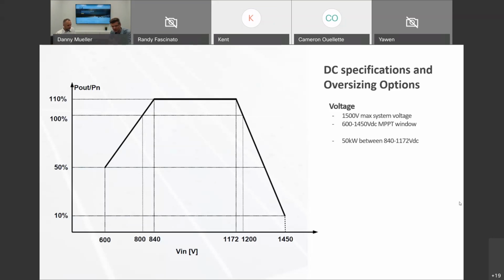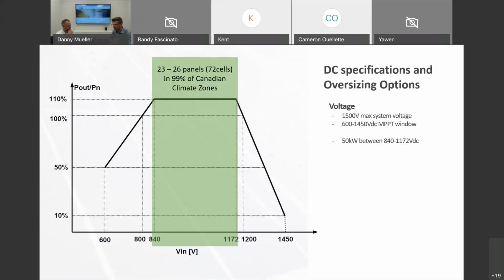The inverter starts at 600 volt. That's typically on the very, very low end of the spectrum, and if you've done your string design properly, you will never reach that point, but it can go down to those lower voltages in a partial shading condition, for example. The system voltage, as Danny mentioned, is 1,500 volts, so you cannot exceed that voltage under any circumstances, otherwise the inverter and DC capacitor will fail. So with any string design, you design for your typical target temperature in the winter. Let's say you have a design at -35 or -40 degrees Celsius, and you adjust with the temperature coefficients of your module. And that leads typically to the following string designs.